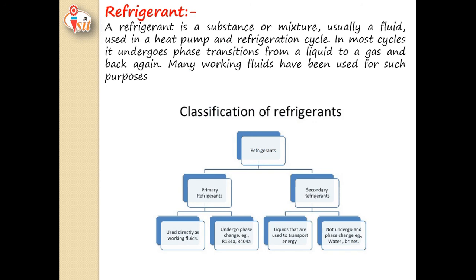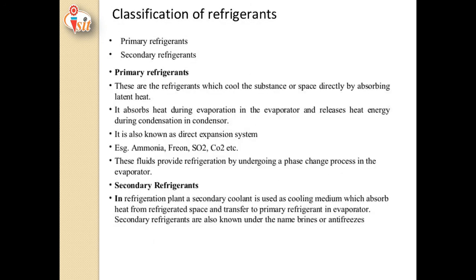Primary refrigerants are those which cool a substance or space directly by absorbing latent heat. They absorb heat during evaporation in the evaporator and release heat energy during condensation in the condenser. In the vapor compression refrigeration system, vapors of refrigerant are compressed in the compressor, forming high-pressure, high-temperature vapors. These are sent to the condenser where phase transformation takes place, converting them into high-pressure, low-temperature liquid refrigerant.